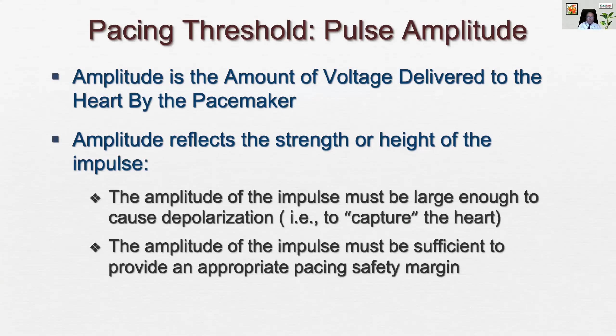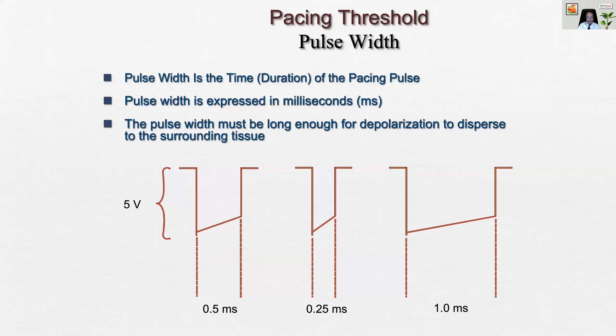We have already discussed that the threshold is the minimum output necessary to capture the myocardium. Pulse width, as I said, is measured in milliseconds. Usually we keep it around 0.4 or 0.5, or it can be changed depending on the requirement. And then there is a thing called the strength duration curve. On the right side, we have the strength duration curve. On the y-axis, we have the threshold: 1 volt, 2 volt, 3 volt, 4 volt, 5 volt. On the horizontal axis, we have the pulse width. Every stimulus has a certain pulse width and voltage. All the impulses which fall above this curve will capture.